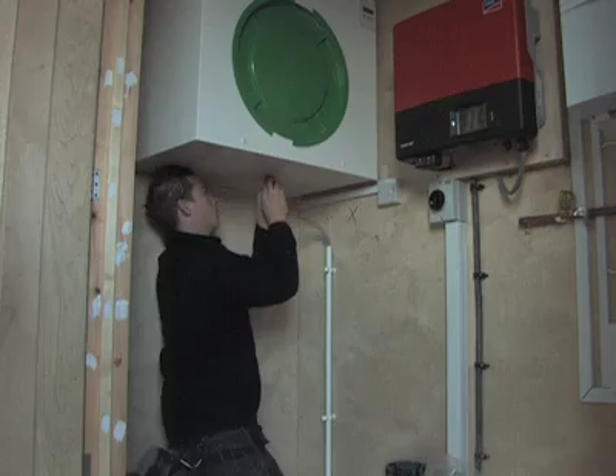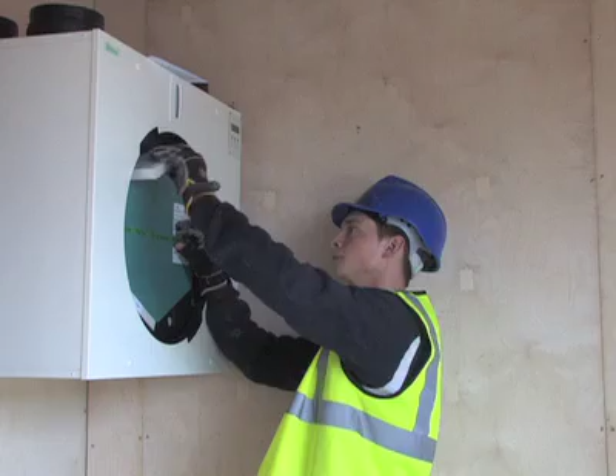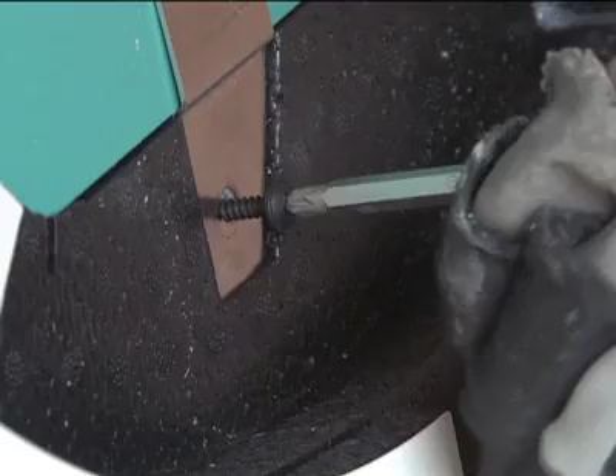The condense drain can now be connected to the waste water via a trap in accordance with Building Regs H1. To fit the drain tube, you need to access the inner casing, removing the filters and heat exchanger and replacing them once complete.